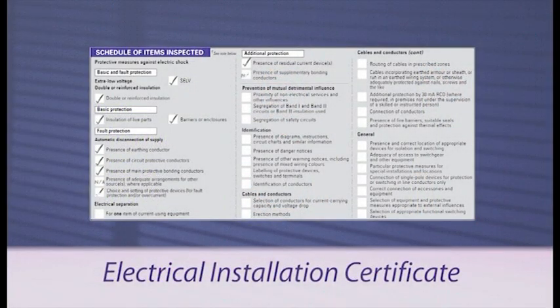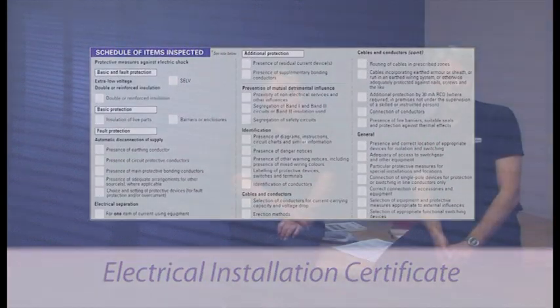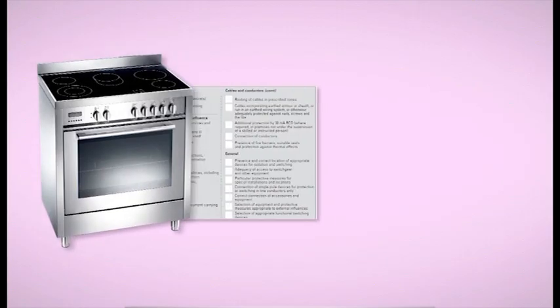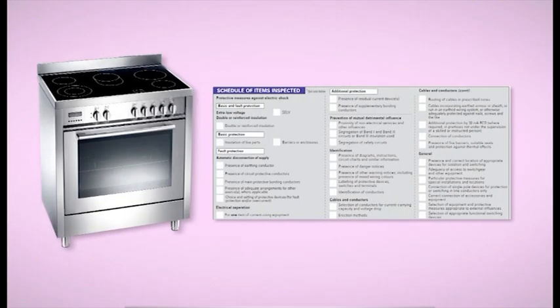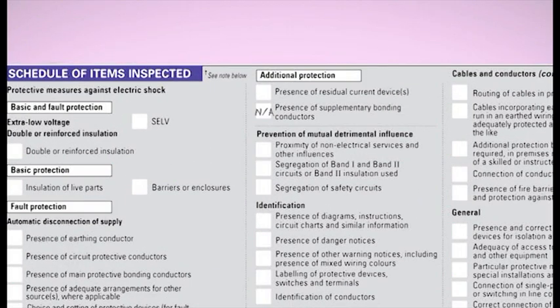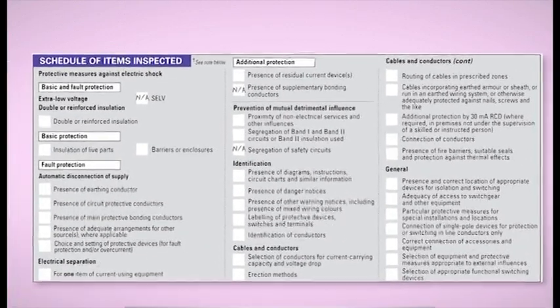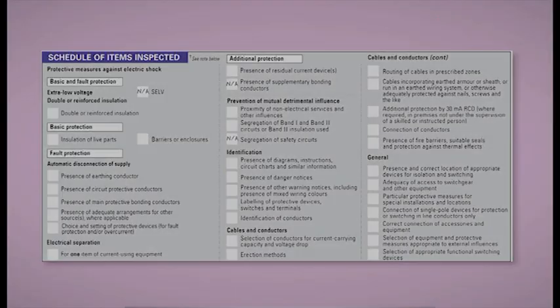Another thing to point out is that no box on the schedule should be left blank. For the electrical installation certificate, there should be a tick or a not applicable in every box. It's important to remember that the inspection schedule only relates to the work that you've carried out. For example, if a new cooker circuit is installed, then more than likely you wouldn't be checking for supplementary bonding, segregation of safety circuits, SELV, etc. And therefore these boxes will have NA.